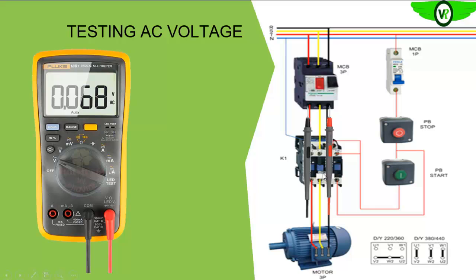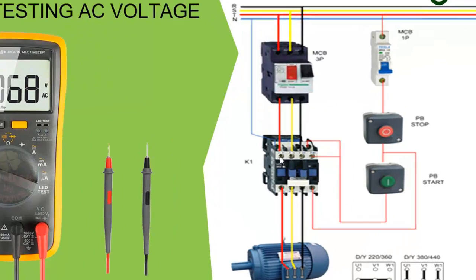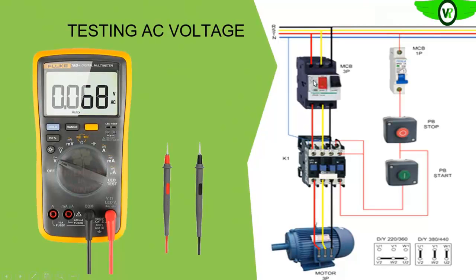That is what it means. So now, for you to test the other components in the circuit, remember we are testing live. You will come down to the contactor. These are the various terminals. Okay, line 1, line 2, line 3. You are supposed to have 415 volts. So once you have that voltage signal at this input terminal to your contactor, that confirms that everything above the contactor is good. The line connecting the contactor and the circuit breaker, the line connecting the circuit breaker and your bus or your input line to the circuitry, they are good. The circuit breaker above the contactor is also good.